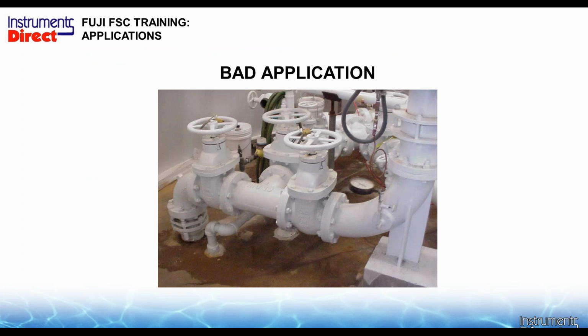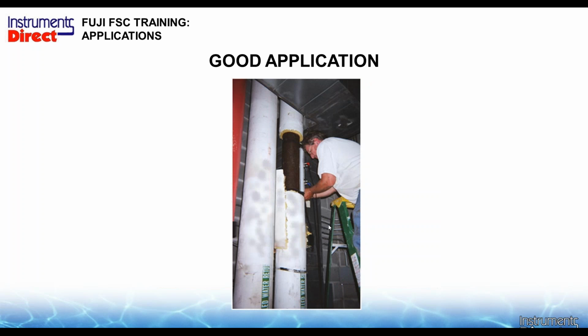Now, every application you see is not going to be perfect, and this usually is what I get to see when I get in the car after driving 100 miles. Here's a bad application like this. No straight run of pipe. So the customer will say, just put it on there, I just wanted to see it read. Step one, never show an ultrasonic flow meter not read on purpose. It's just a bad mindset, and that's the only thing anybody will remember. If you really want to monitor flow in this application, you have one choice or two choices. You need to go upstream or downstream, and somebody may have to get out a backhoe if you really, really, really want to monitor flow.